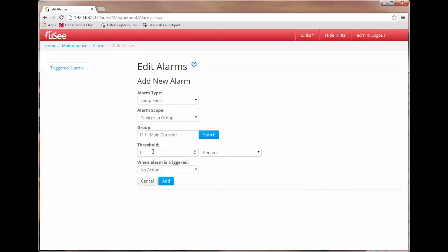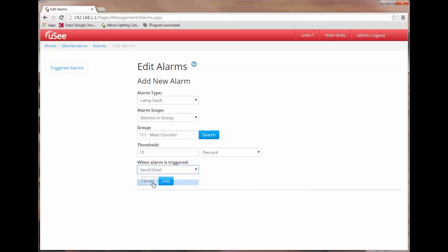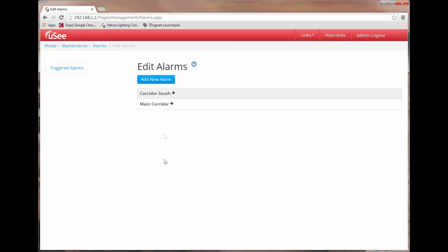Now we get a slightly different choice for threshold. I can either set my threshold by percentage of devices within the group or by number of devices in a group. Now you can see this would be very useful. If I had a group which consisted of let's say 30 devices then I could set a threshold that said please alarm me if more than four lamp failures occur in the group, or if more than 10% of devices have failed in that group. And if this threshold is met I could actually say please send me an email and I'll add that.